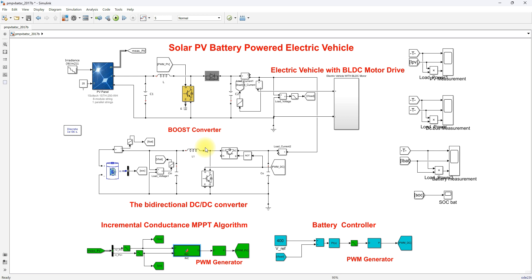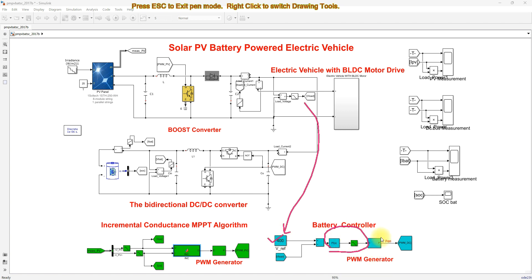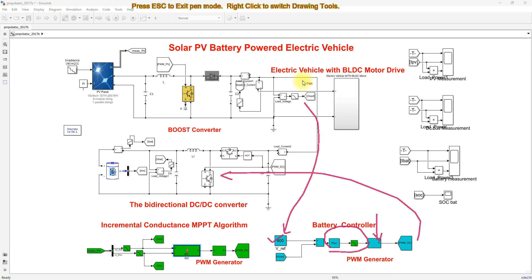The bidirectional converter can take power from the solar PV or supply power to the DC bus. It is controlled by a voltage control method: the DC bus voltage is compared with a reference voltage, processed by a PI controller and then a PWM generator, which generates PWM pulses for the bidirectional converter to maintain DC bus voltage constant and change the direction of current flow according to power balance in the system.